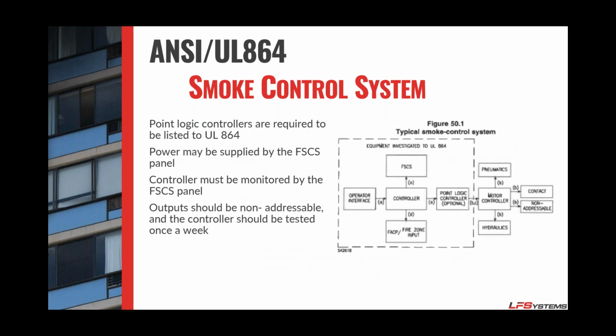Better yet, we'll just look at this quick diagram provided by UL. It basically says anything inside the dotted box needs to be investigated and listed to UL 864. So any controllers, operator interfaces, your fire smoke control station or control panel. There's a box over here called the point logic controller. We'll get to that in a second. Outside the box, your motor controller, your VFD, anything that's controlling the motor does not need to be listed unless it's making decisions. Once it starts making decisions, it goes back into this side, right?